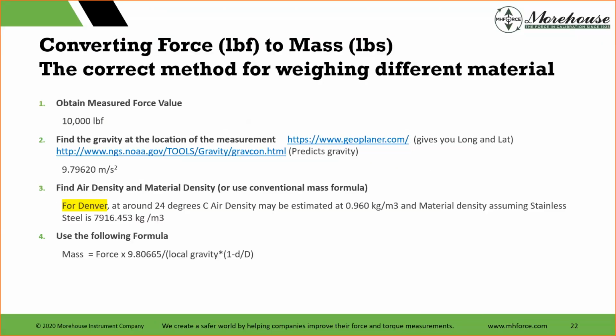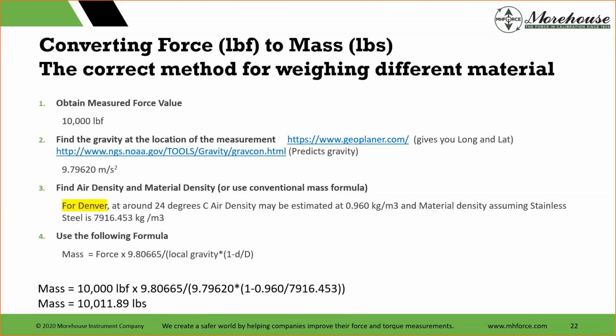And then you go to that NOAA site, which I referenced, that predicts your gravity. So if we were to say here, find the air density and material density for Denver, we could go look up where Denver is, and I added some things for material density, assuming stainless steel and whatnot, and I did the formula. So mass equals force, and there's also a formula for force. You can just redo this formula, or we have it on our website. So use that formula. What this is essentially showing is that if we did a calibration here in force, sent that device to Denver, and they wanted to convert it back to mass for, say, weighing, here's the formula.